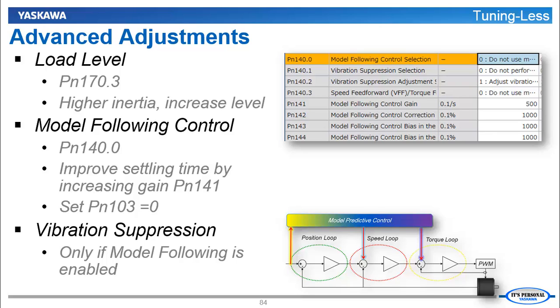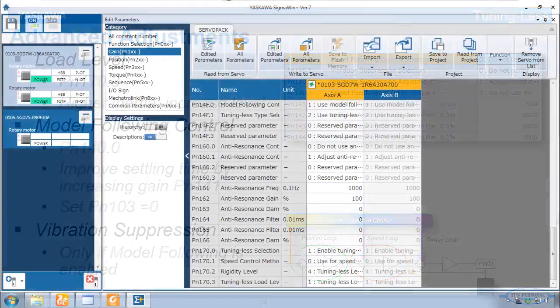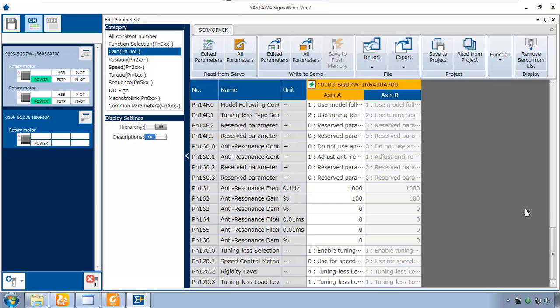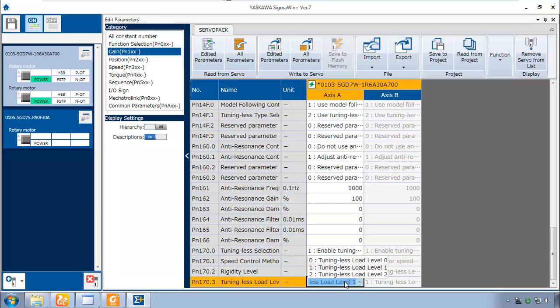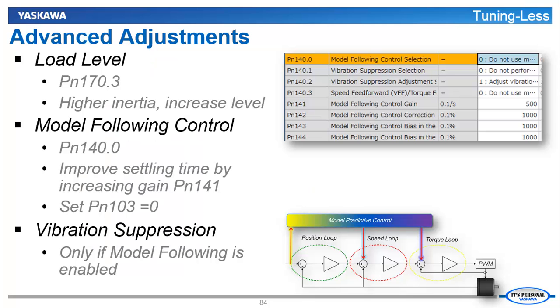If those two parameters just aren't giving you the response you need. And you still need the adaptive response of tuningless. You might want to look at some advanced adjustments. One of them is the load level. Load level is parameter 170. We've had it set here to level number 1. But there is also a level 0 for light loads and level 2 for heavier higher inertia loads.